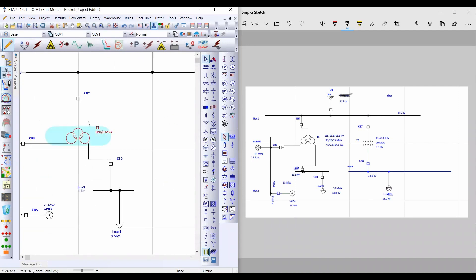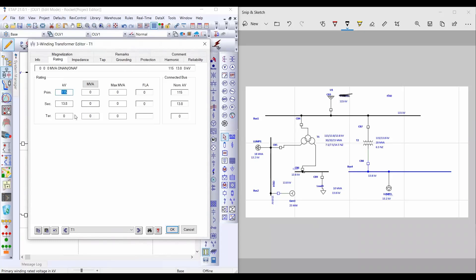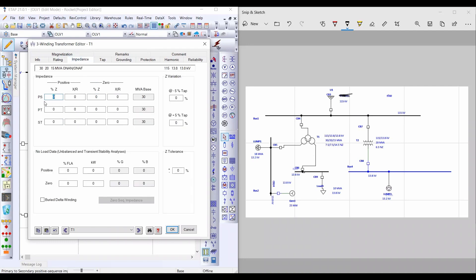Then double left-click on the three-winding transformer. From Rating, the tertiary side equals 13.8 kV, the primary MVA is 30, secondary is 20, and tertiary is 15 MVA. From Impedance, insert the impedance values between primary and secondary, primary and tertiary, and secondary and tertiary: 7.5%, 7.5%, and 14.5% respectively. The X/R ratio will be 12, 12, and 12.